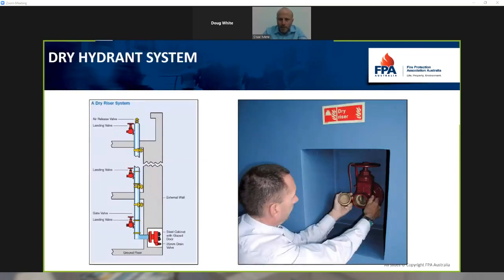So very briefly here about the dry hydrant system. As I said, it is not connected to a water supply. It requires the fire brigade to come in and connect here at the booster at the bottom. And this is essentially a dry pipe that runs up the building, usually in the fire isolated stair, that will service all of the fire hydrants.